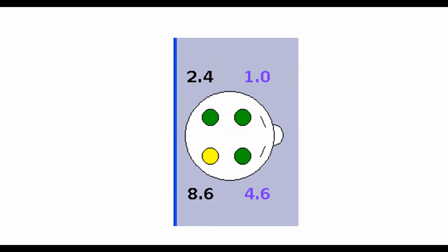If you're using needles, this is not an issue, right? You go through the skin and your impedance is practically zero. If you're scrubbing the skin, then you're going to want to make sure that you're scrubbing it enough to keep your electrodes under 5. My personal preference is that under 10 is the minimum acceptance. I want it under 5, and the lower the better. But again, our babies have very fragile skin, and you have to be careful that you're exfoliating but not excoriating the skin. That can oftentimes be a challenge.